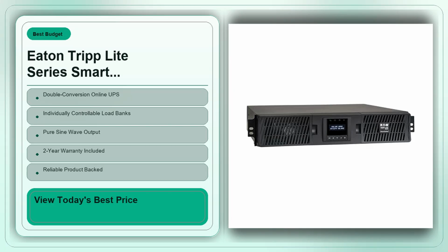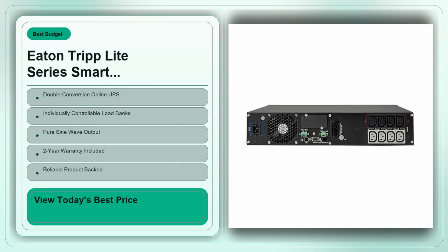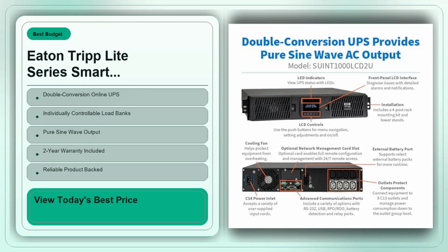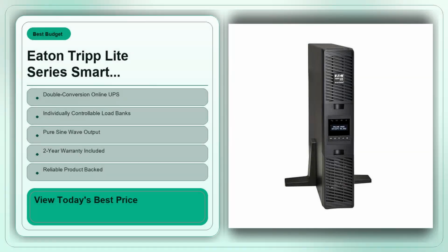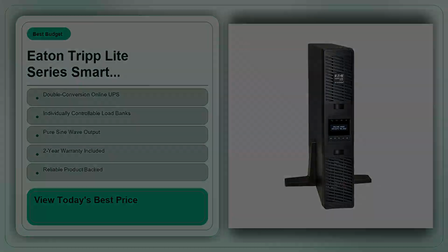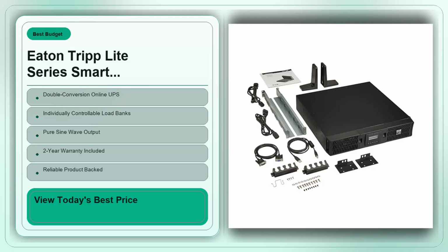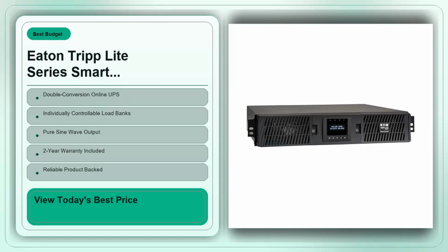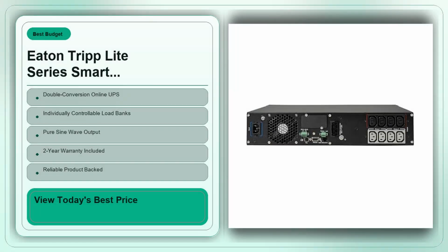Let's start with the core problem most buyers face. You need reliable, clean power for critical gear, but you also don't want to waste money on a unit that's either overkill or underdelivered. The smart part of this UPS is the double conversion, online design. Unlike line interactive models that switch to battery only when the voltage dips, this unit constantly runs your equipment through the inverter. The result is a true pure sine wave output, which is the gold standard for sensitive hardware. Think network switches, small servers, or a home theater preamp that hates any distortion in the power line.